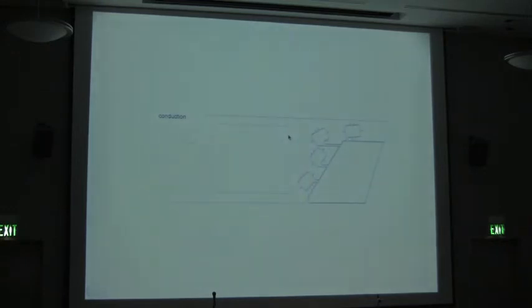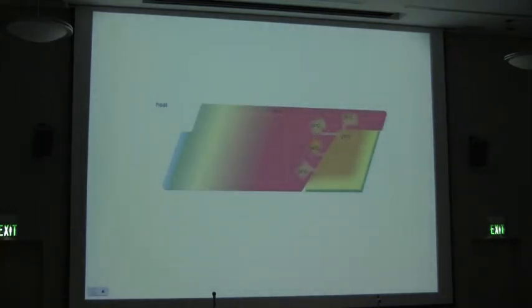We could see it here. Yes, we could warm, because the temperature of the air of the swimming pool has to be at 28 degrees Celsius. So we warm with this air. We warm the fitting room, the changing room here, but of course we don't want the humidity of the air, of the water of the pool, to go in the changing room. So we take the breathing air from this side, and it goes inside this small pocket. But in between, there is just a metallic conductive wall between this and the inside, so it means that it is warmed by the air, but the humidity of the air doesn't go inside.